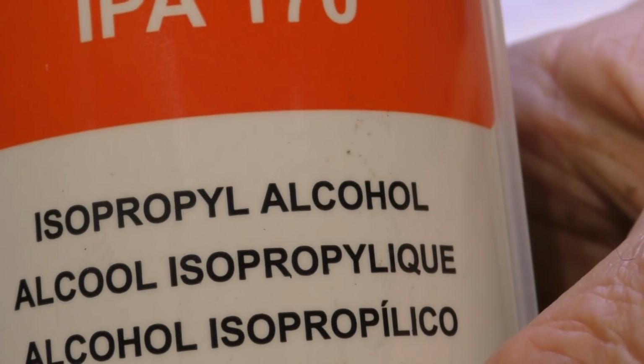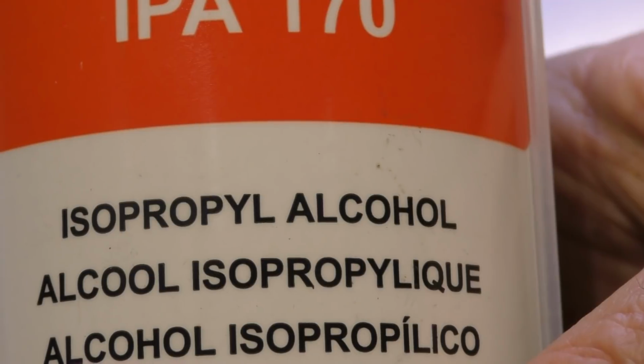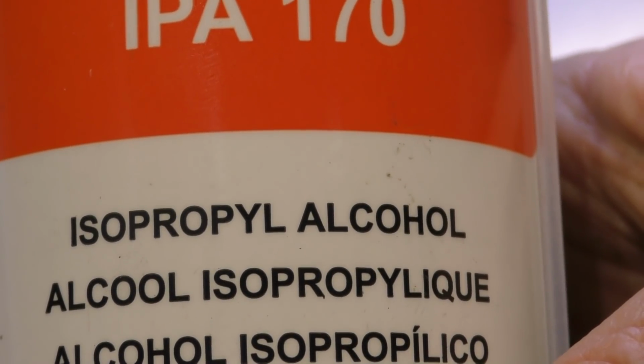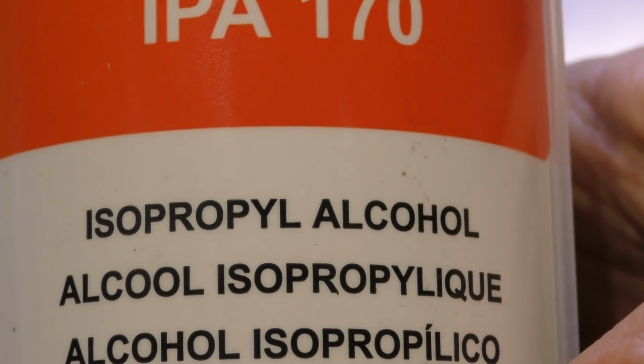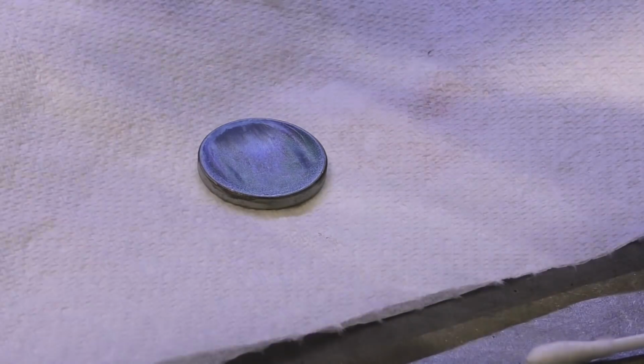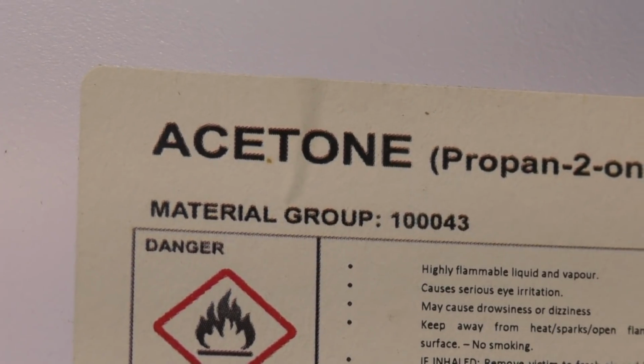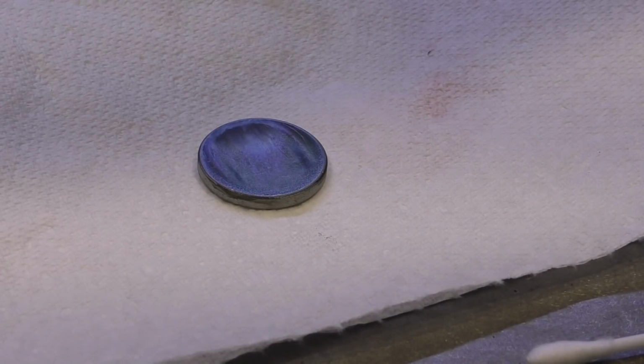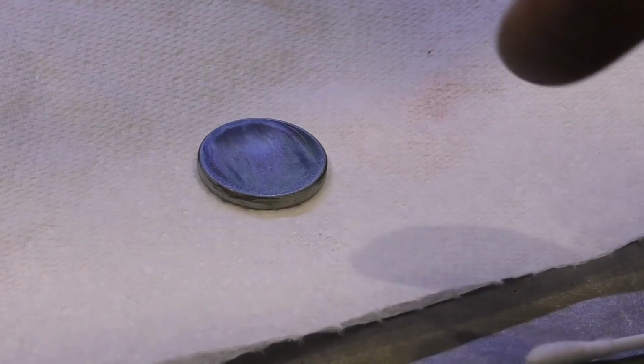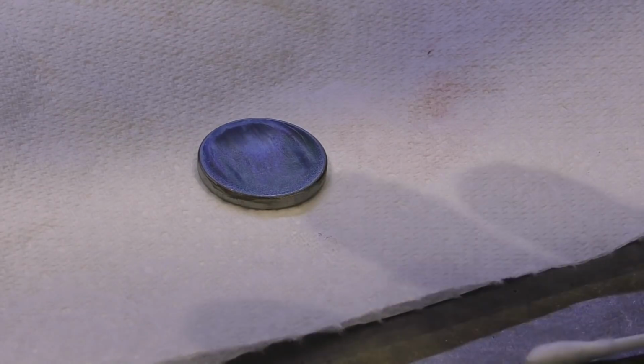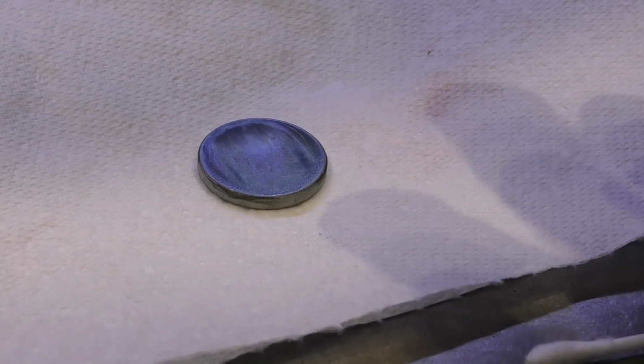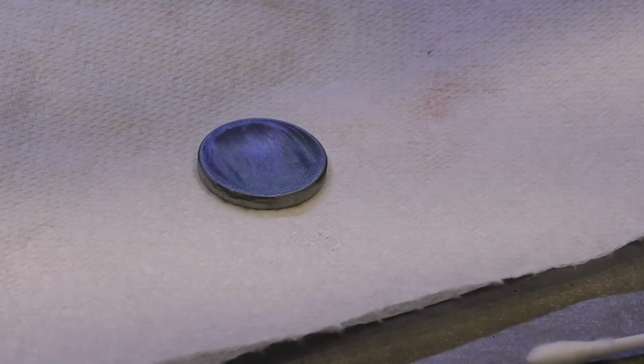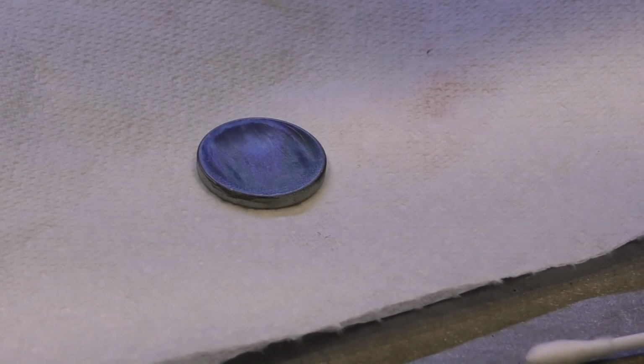The most gentle cleaning agent that you can use is isopropyl alcohol, and you can use this on lenses as well. So if that fails to clean your mirror, there is another stage that you can go to which is slightly more aggressive, and here it is, acetone. You can do acetone cleaning on a mirror like this because it's molybdenum. You cannot use acetone on anything that looks as though it's gold coated, because the gold coating is very, very thin, so they may be more expensive to buy than these relatively cheap, and these are only about $5 each, mirrors.